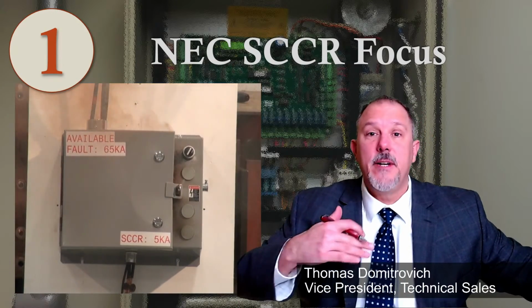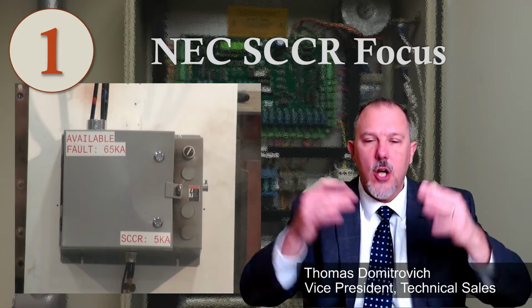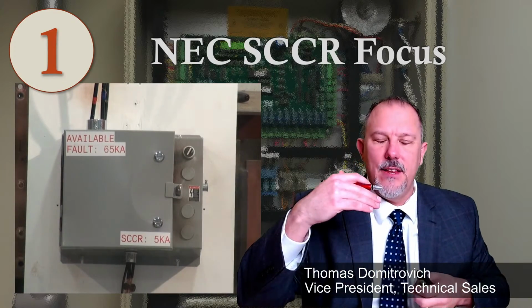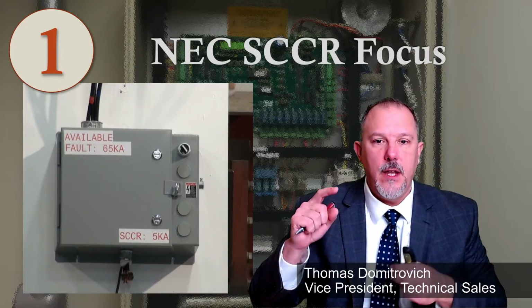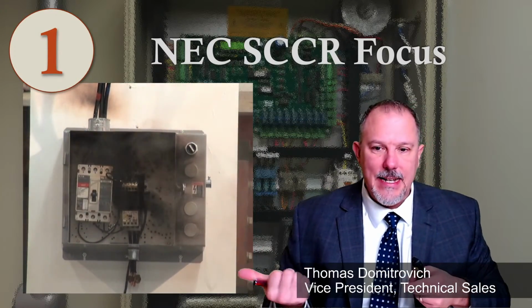So that looks like my shirt after Thanksgiving dinner, right? What we did there was the components inside could not stand the amount of fault current flowing through that equipment. That is a short circuit current rating. A short circuit current rating is not trying to stop the flow of current. You'll notice that the problem that we created is not in the equipment. It's down here. We basically created a bolted fault downstream of this equipment that the equipment was not rated for.